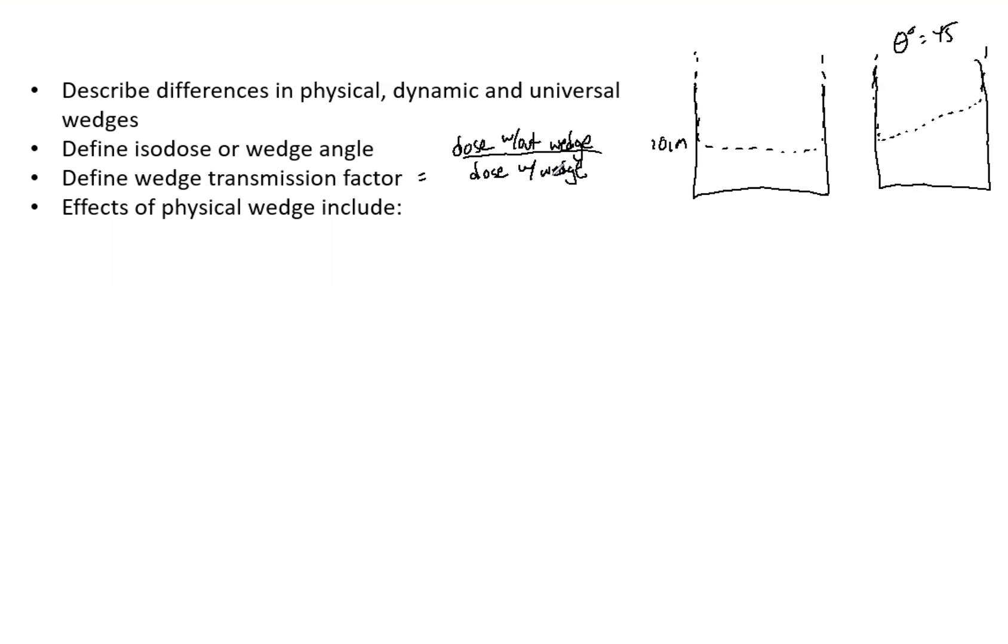Small topic, but be sure you know the differences. Elekta machines use universal wedges, Varian machines use physical and dynamic wedges. Understand the differences, what machines use what, and the advantages of each one. If you have any questions, please comment below. Thanks for watching and happy studying.